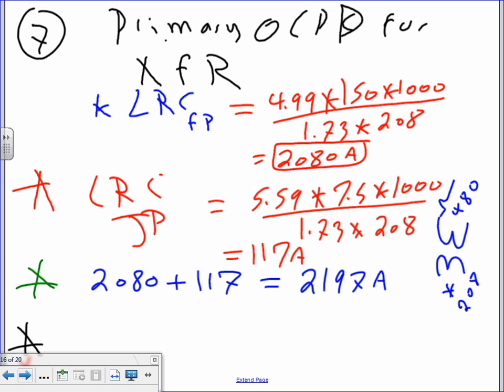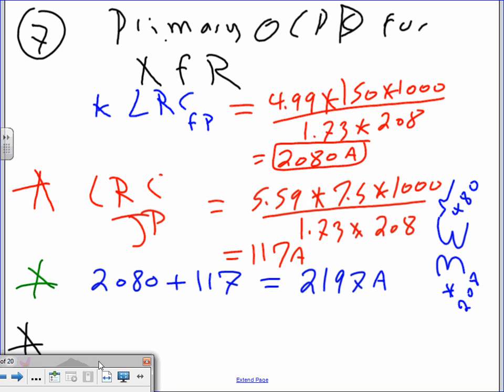Now I did the calculation on the 208 side, I need to transfer it to the 480. What do you do? Multiply it by the voltage ratio. Because an amp here will be different than an amp here. An amp here will be 208 divided by 480 times the amp, because it transferred. That's what transformers do for a living. They transfer it.